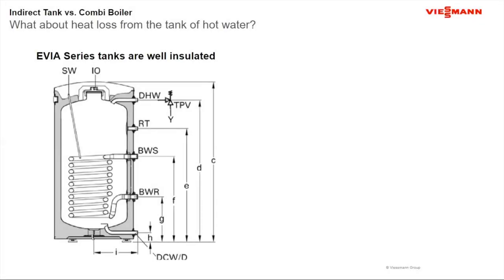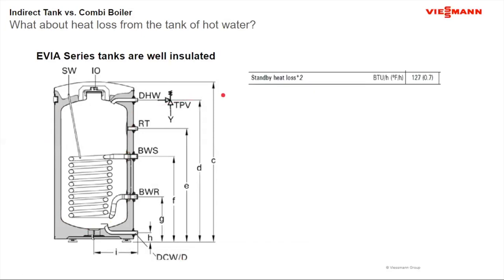Now, one of the other negatives that tends to be thrown in the direction of an indirect water heater is about the fact that I have a tank of water sitting there warm in the basement of the house, losing heat because I don't use that hot water 24 hours a day. The thing is, with water heaters, the water heaters are always well insulated, okay? Again, I always tend to stick with the 42 as the tank that I talk about when I talk about indirect style water heaters versus combi boilers. But if you look at that 42 gallon tank, the heat loss off that tank is 127 BTUs per hour. That represents a heat loss of about 0.7 degrees Fahrenheit.